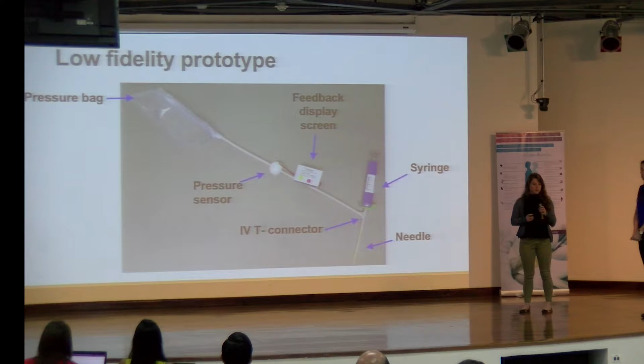That system essentially uses pressurized saline with a pressure sensor, and what we've changed is the feedback system. This feedback system is going to tell the doctor if the placement has been successful in the vein or unsuccessfully placed in the artery. Another key feature of our device is that the feedback system is clippable. We think it's very important that the doctor shouldn't have to be looking back at a screen while performing the relatively short procedure. So it can be clipped directly onto the non-compressive tubing, or removed and placed anywhere close to the patient that's in the line of view.